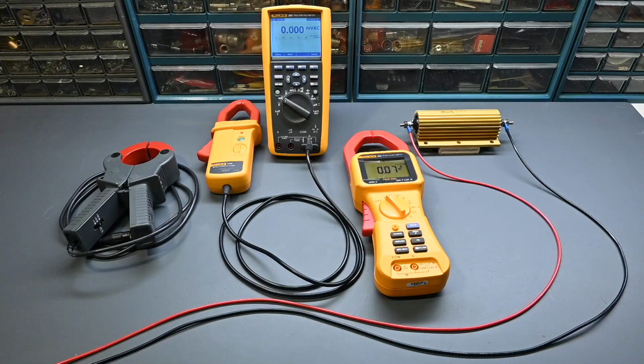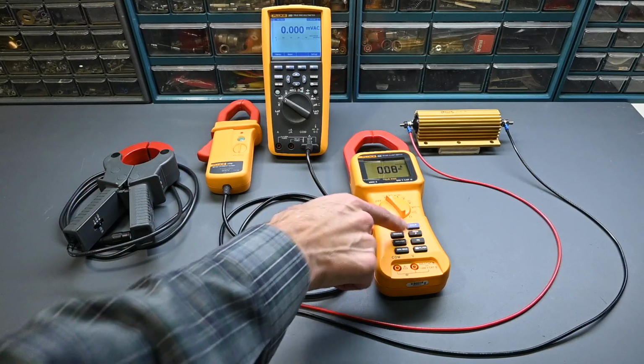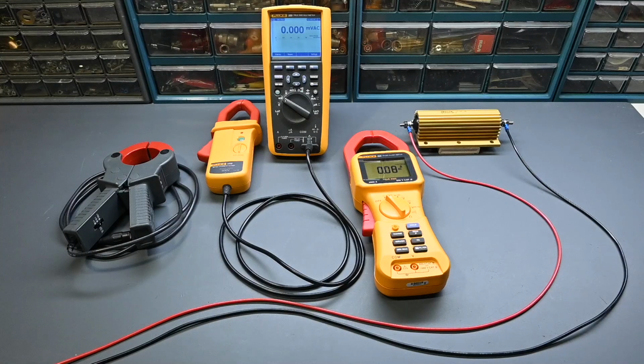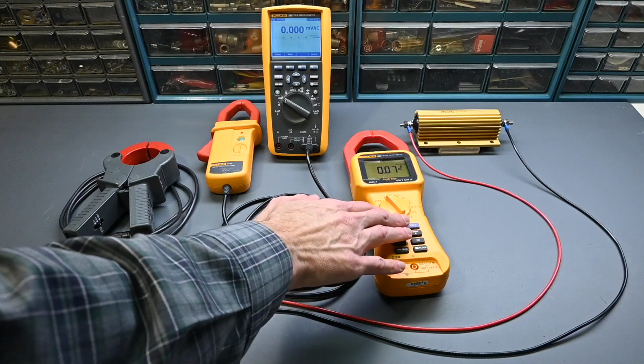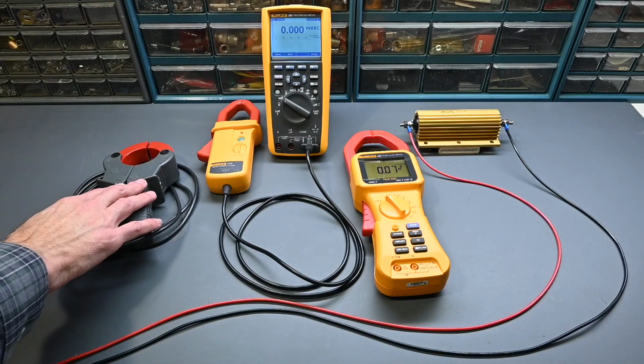Now in the DC current mode, the Hall effect sensor requires zeroing before you take the measurement. So on this current clamp there's a 0 adjust right here. On this current clamp there's a 0 setting right here. If you don't zero the clamp, you'll have an offset voltage that would interfere with the measurement you're trying to take. But in the AC current mode on these clamps, the 0 adjust is not necessary, and there's no zeroing on a clamp like this.